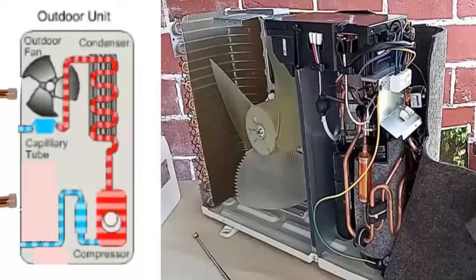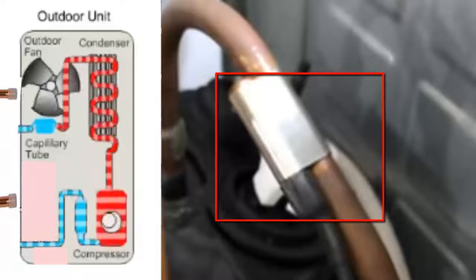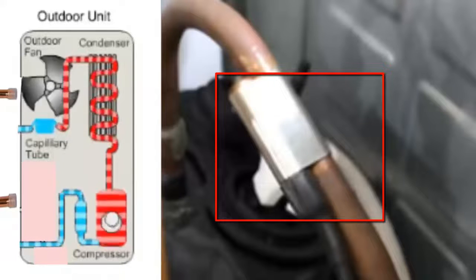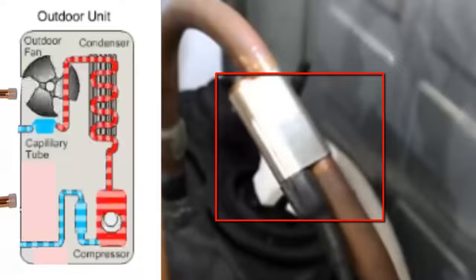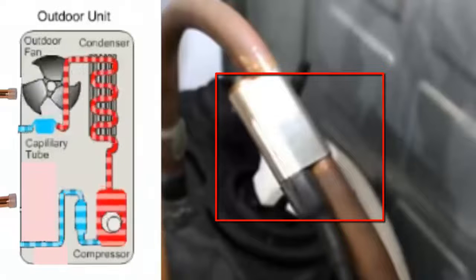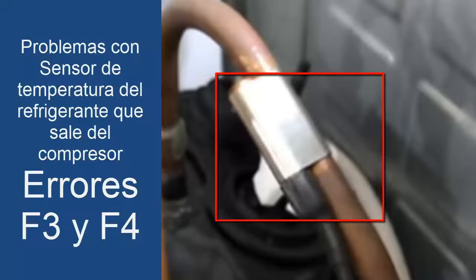We can also find a sensor at the compressor discharge, where the high-pressure refrigerant exits at high temperature through the thinner tube of the compressor. This sensor measures the temperature value to protect the compressor so it does not exceed safe values. This is very important, especially when working with refrigerants with high temperature discharge values such as R32. When this sensor has a problem, the codes that are presented are generally F3 and F4.